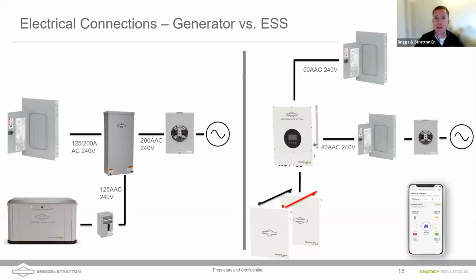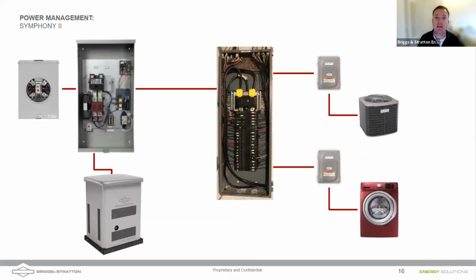We have grid, meter can, non-backed up loads, and inside the inverter is the transfer switch. It's a microgrid interconnect device, or a MID, I think it's what it's called. And that will allow us to transfer, disconnect ourselves from grid, and then start using energy stored in the batteries to power loads in our critical load subpanel as well.